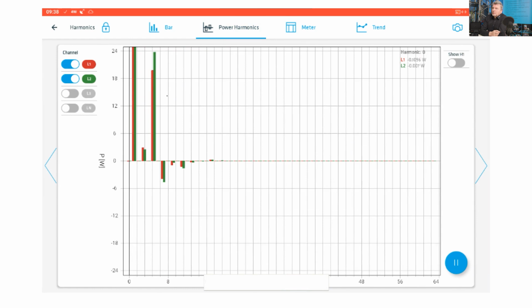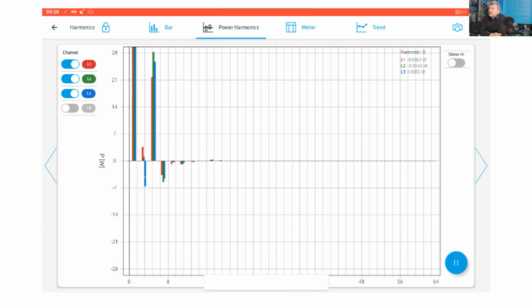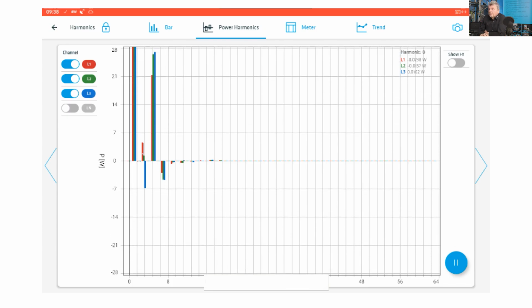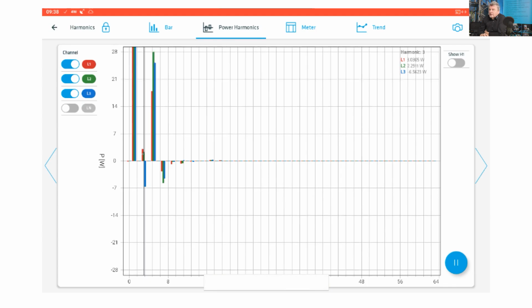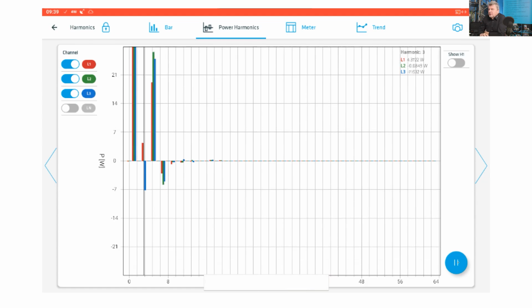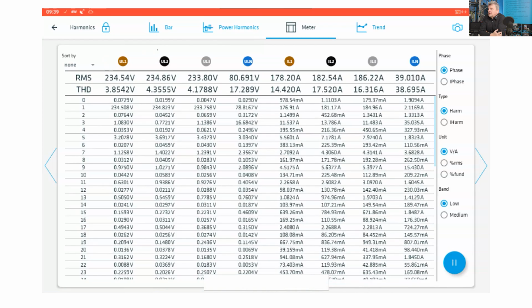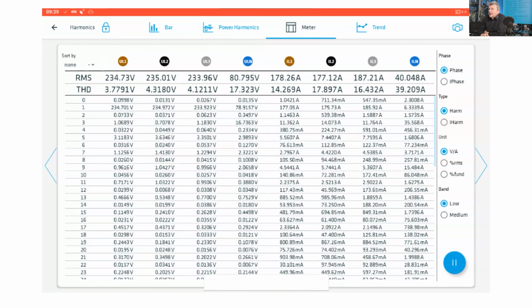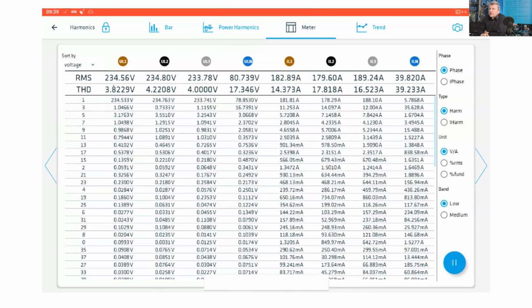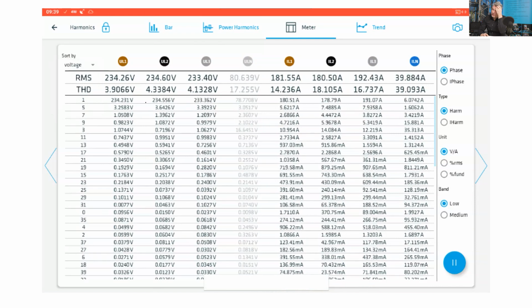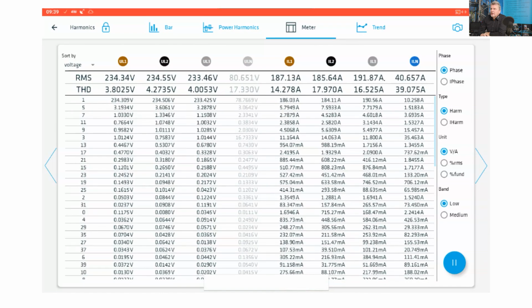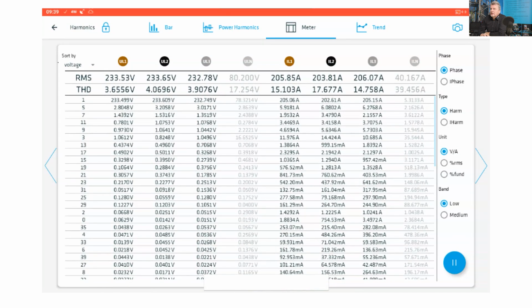Then we have the power harmonics view, which is available for 4-wire connection, not for three-wire or open delta, because it is related to the phase measurement. We can check which harmonics are generated and which harmonics are imported from the network. So this is a direct online view. The meter screen shows numerical data, and you can sort by the voltage, so you can see which voltage harmonic is the highest, or related to the current.